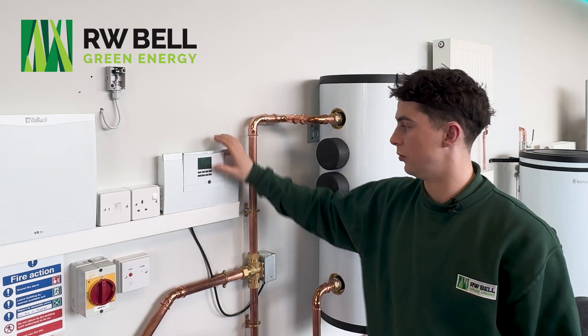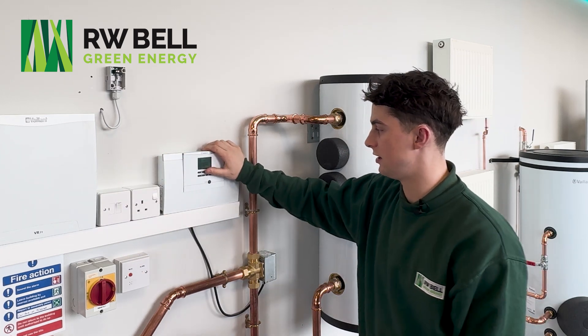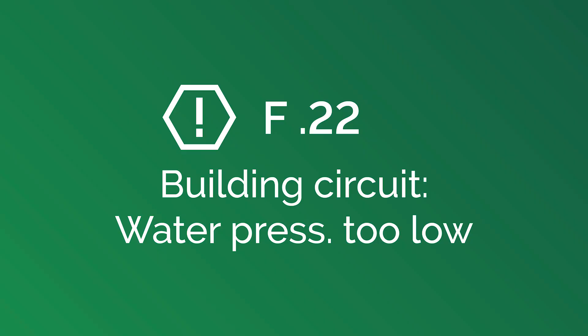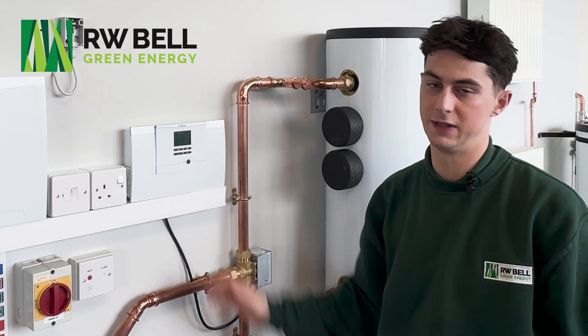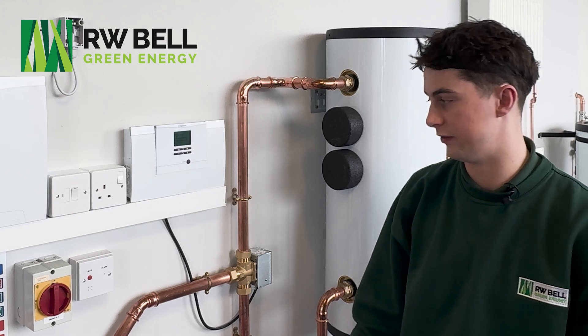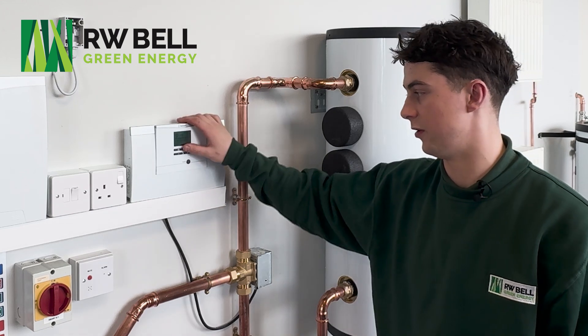When you come to the screen, it would normally present you with an F22 fault, which means your building pressure is too low in your heating system. This means that the heat pump will not operate until you've resolved this fault.